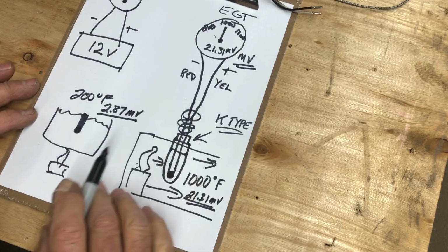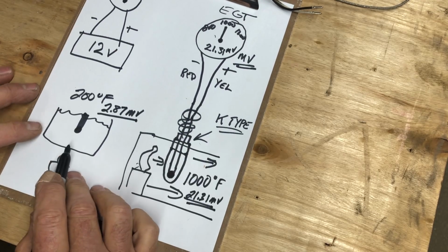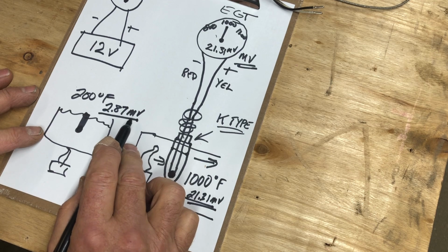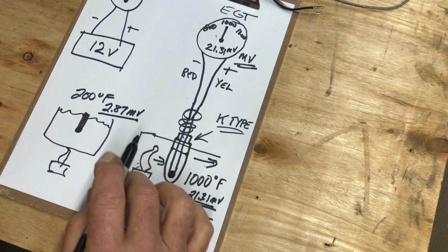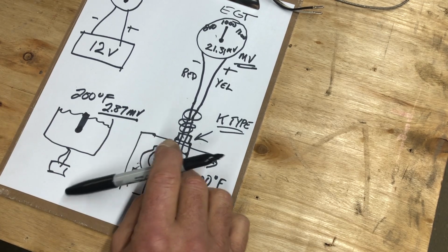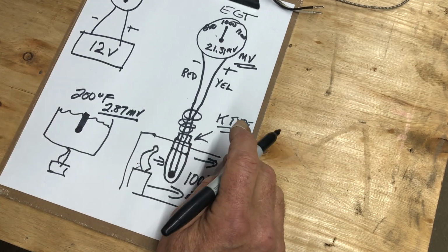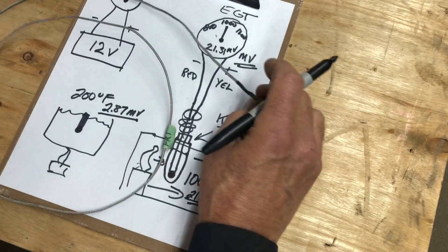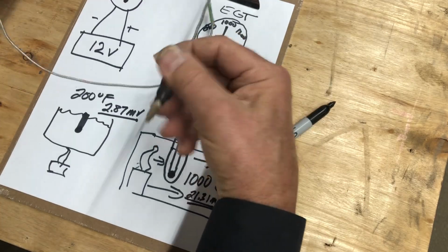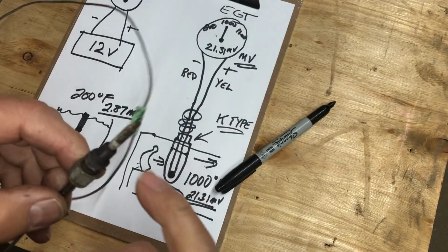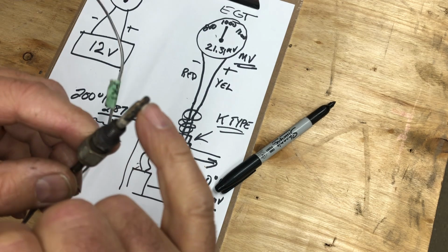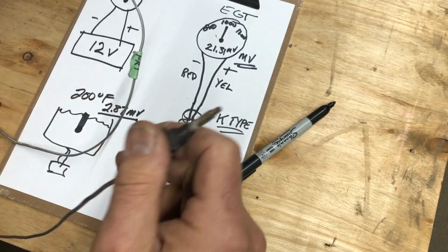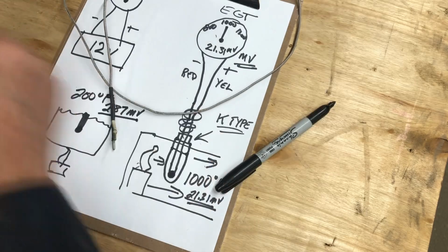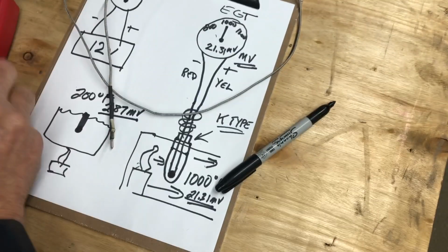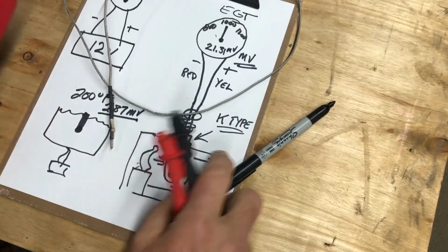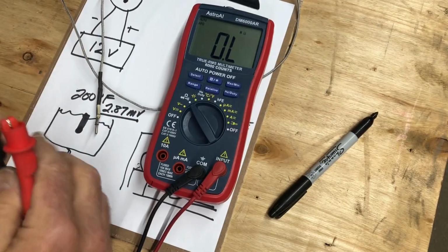So we can actually test these just like this in water and see what the output is. The other thing we can do is check the resistance on it. So here is a probe, this one is an actual real Westac probe, and you can see the end of it is crimped down here, this is what they call a grounded probe. Anyway, let's hook up the ohm meter and find out what we get.